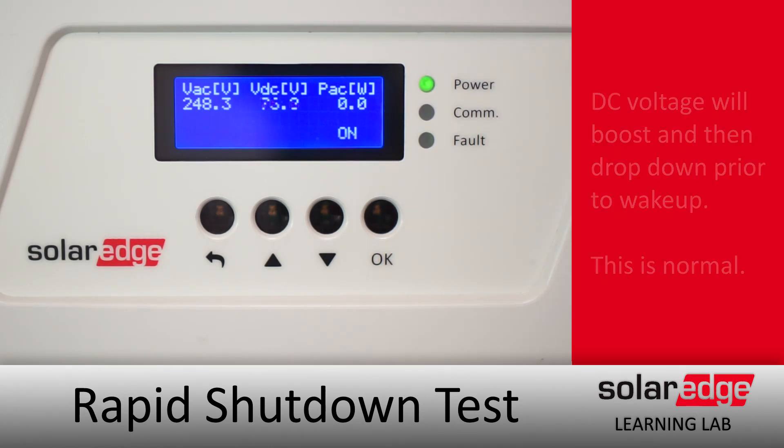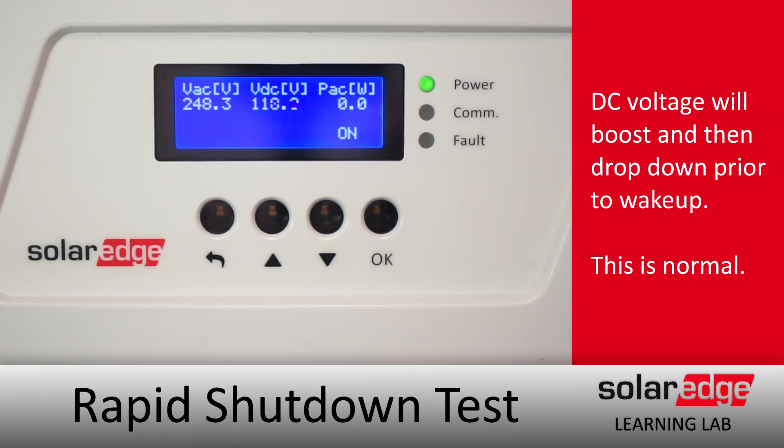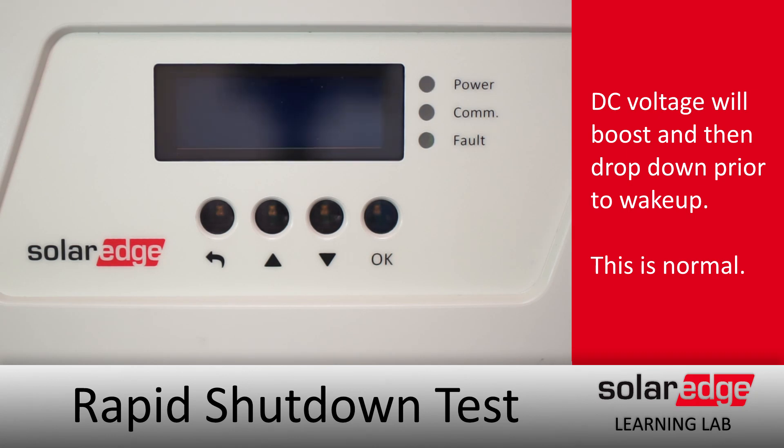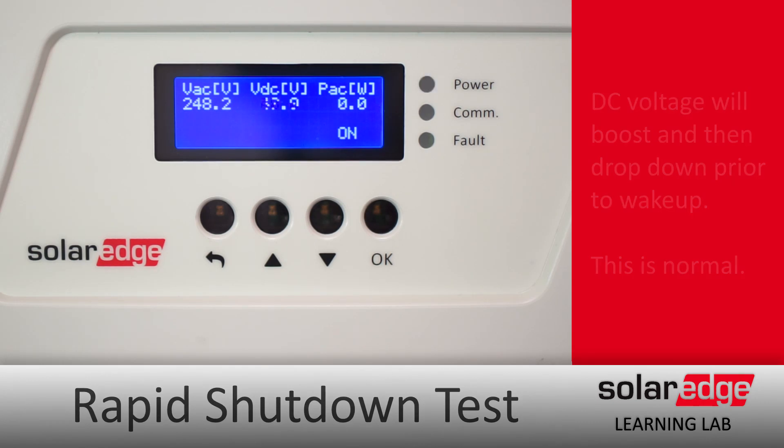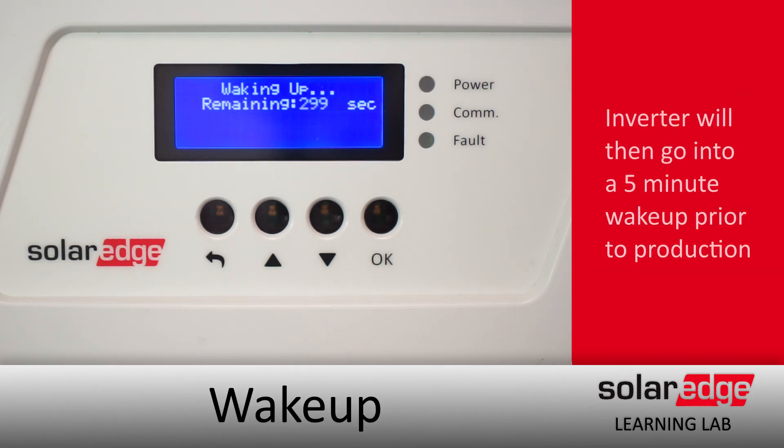After that, the DC voltage is going to drop back down. Don't worry when this happens — this is absolutely normal. This is the inverter testing the DC rapid shutdown. Following optimizer detection, string detection, and rapid shutdown test, the inverter will go into a five-minute wake-up mode and then produce as normal.